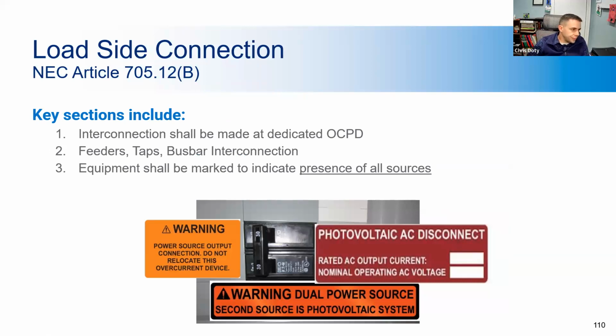So Article 705.12(B) covers the requirements for load side connections. This label is required for when the 120% rule is being used to add additional PV current to the bus in excess of its rating. This requires that if you're going to add additional power to the bus, the source of PV power must be at the opposite end of the bus so as not to overload the bus, as we've seen already.